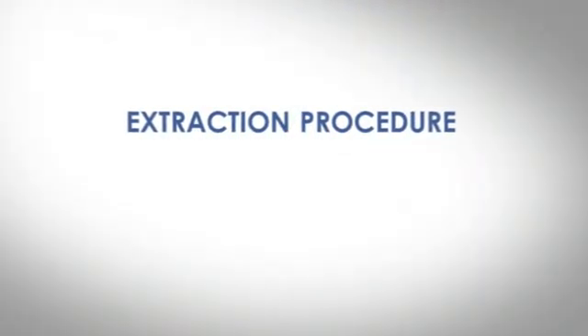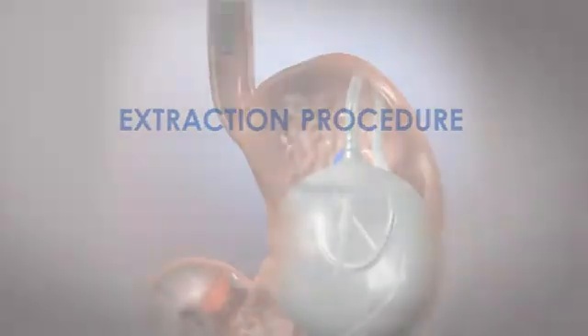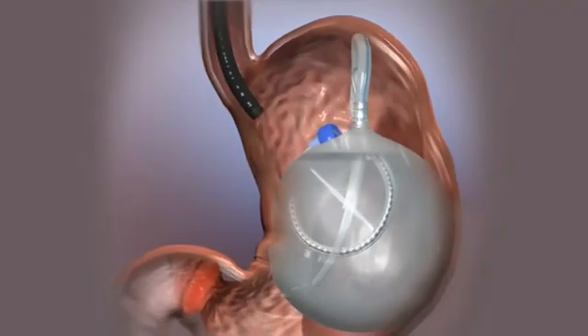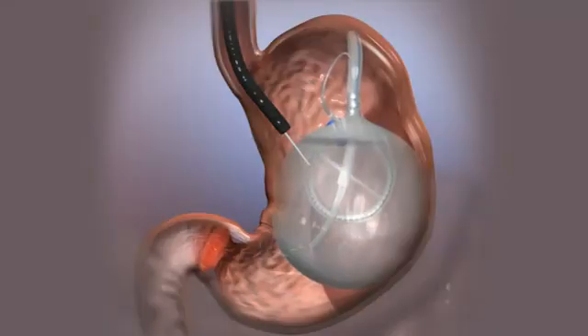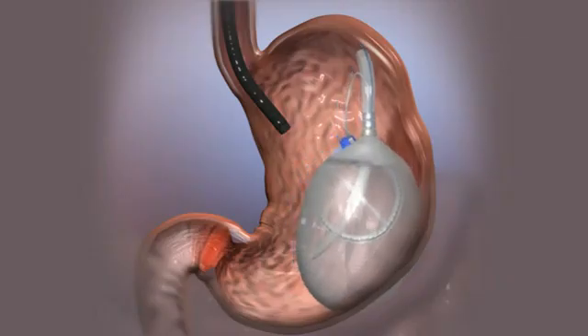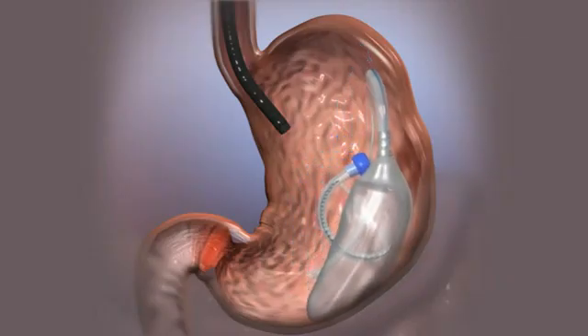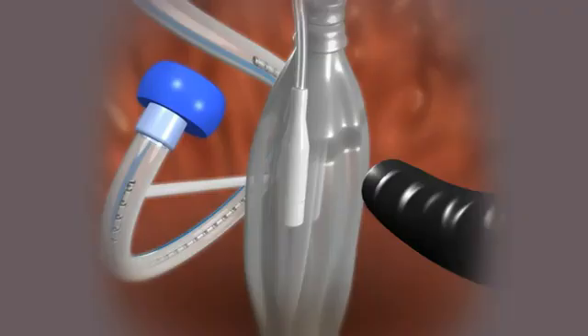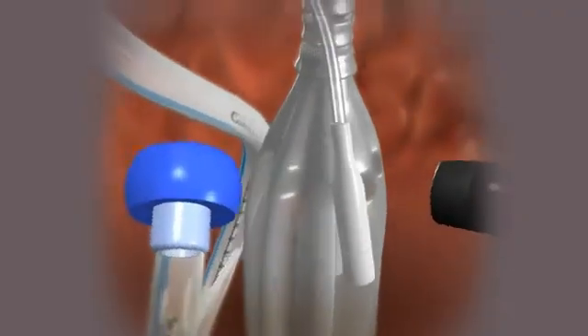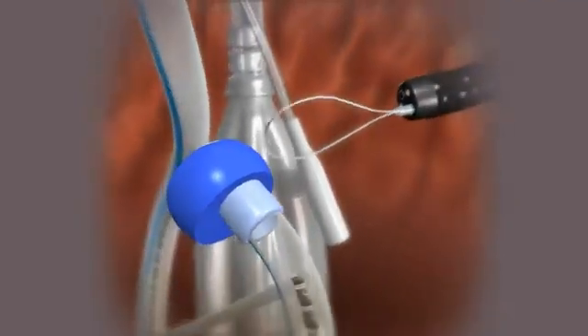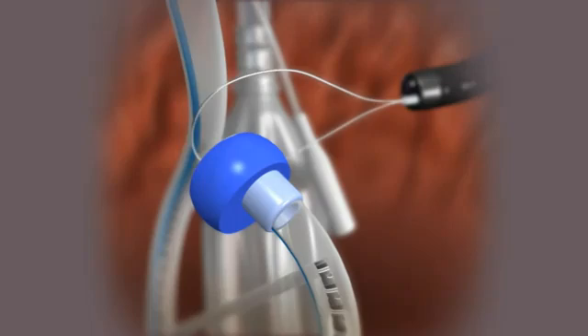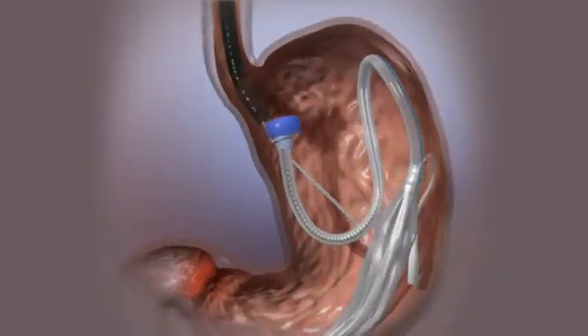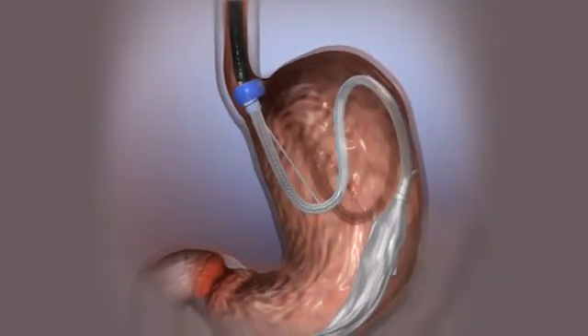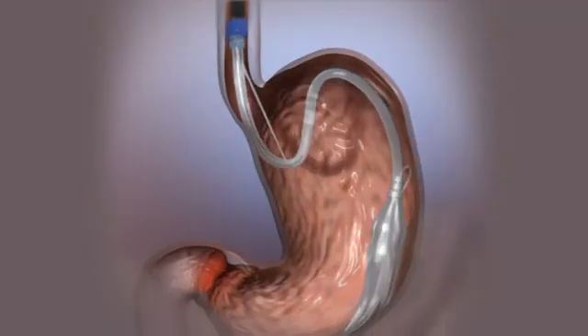Extraction procedure. A needle catheter is inserted to puncture the balloon, or the balloon may be deflated via the inflation valve, as described in the adjustment section. After the balloon has fully emptied, the blue clasp is captured with a polypectomy snare and pulled to the tip of the endoscope. The endoscope and snared clasp are pulled out slowly and gently while twisting the scope to help it pass the gastroesophageal junction.